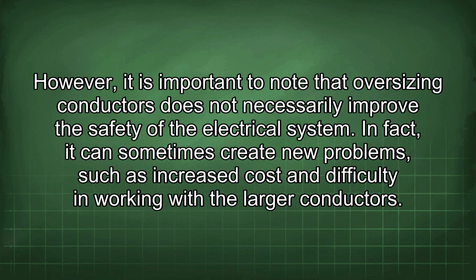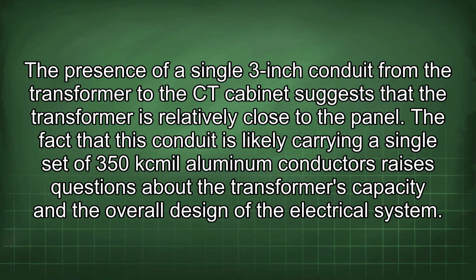The presence of a single 3-inch conduit from the transformer to the CT cabinet suggests that the transformer is relatively close to the panel. The fact that this conduit is likely carrying a single set of 350 kcmil aluminum conductors raises questions about the transformer's capacity and the overall design of the electrical system.